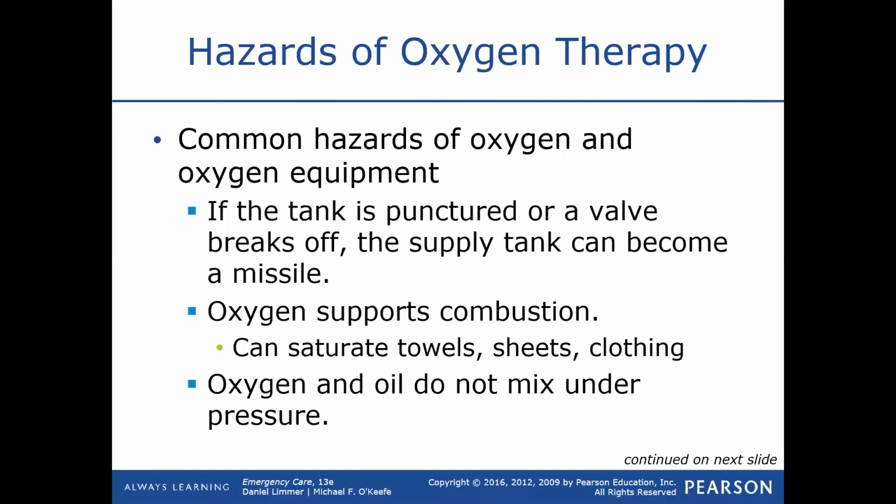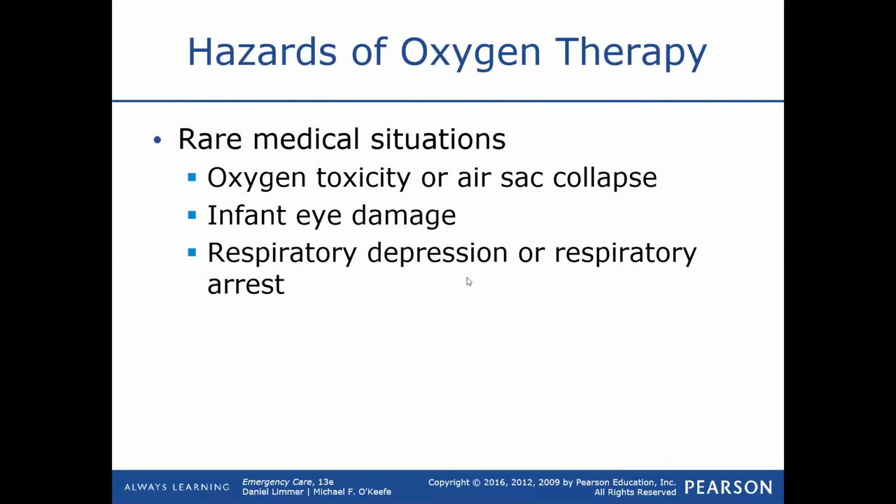Oxygen supports combustion, as we talked about. It can saturate towels, sheets, clothing, all kinds of stuff. And oxygen and oil do not mix under pressure. So that's why we need to be careful, with our water-based lube for our airways that we talked about. You don't ever use oil-based lube to lubricate your regulator or anything like that, because the two of them react to each other.